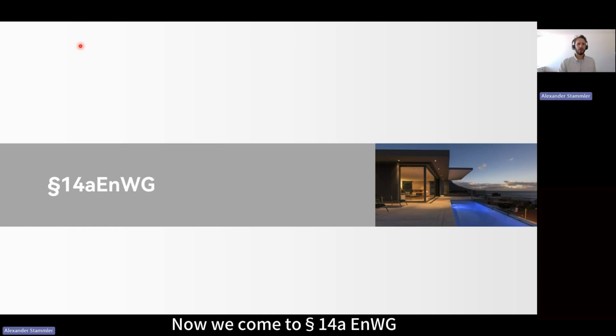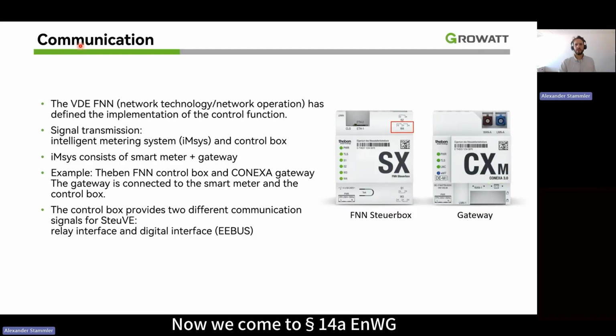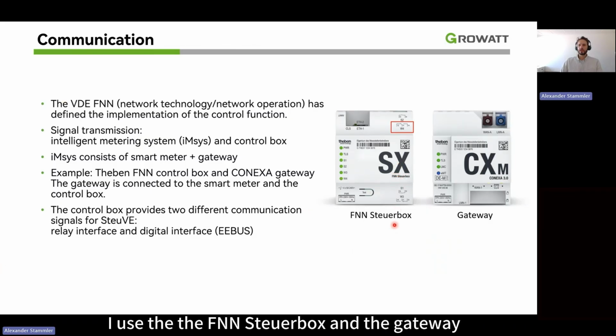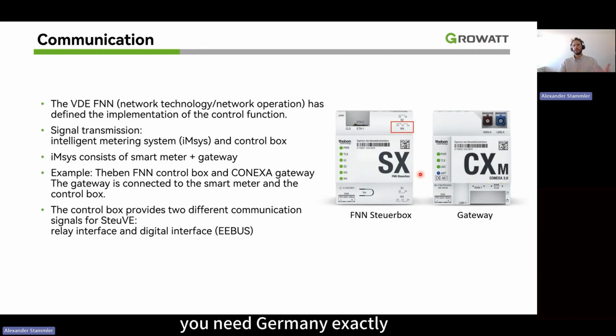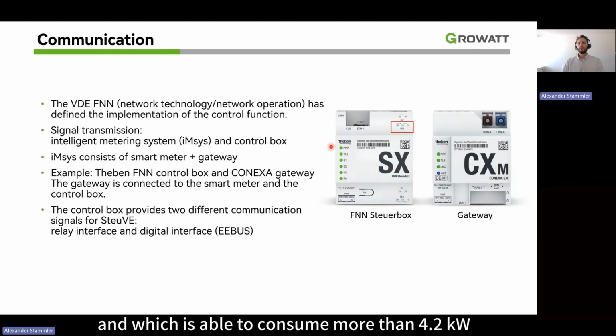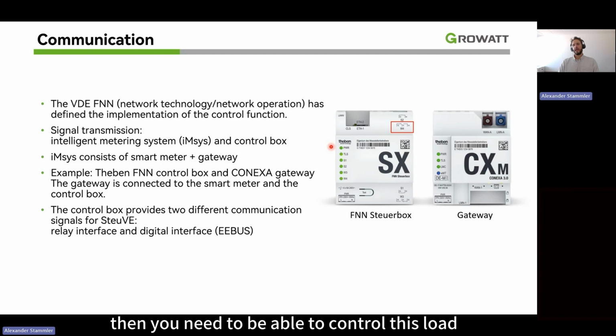Now we come to paragraph 14a EnWG. So I use, as an example, the FNN Steuerbox and the gateway. So you need in Germany, if you have a load which is controllable and which is able to consume more than 4.2 kilowatts, then you need to be able to control this load. So that the grid provider can say, okay, now we have a bottleneck. We have not enough energy in the grid. We want all these big loads to reduce their consumption to a maximum of 4.2 kilowatt.